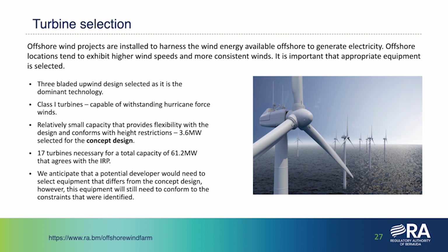We opted for a relatively small capacity turbine, mainly to provide flexibility. The Bermuda grid is not huge, so opting for the largest possible turbines could mean a single turbine forms a disproportionate share of generation capacity, creating security of supply issues. For example, if a 15 megawatt turbine trips, in a grid with demand as low as 30 megawatts at certain times, that would mean a blackout. So smaller turbines provide more flexibility, and that was the main reason for the selection.